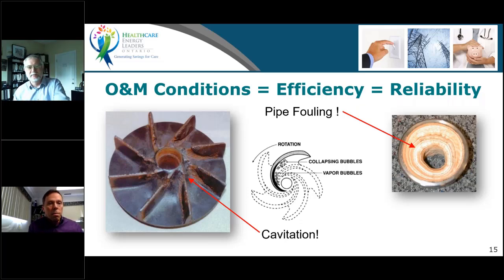The other thing that can happen is the system can change. Now this is a small, I think, 4-inch pipe that had precipitate built up over time. So the 4-inch pipe became a 1-inch pipe. Years and years ago, I had a gentleman come to a workshop that we did, and he had a photograph, and I wish I had taken a picture of it at the time. He had this little 4x6 photograph of an 8-inch pipe on a chiller, on a chilled water system, and he had the same kind of constriction. Now, this was from a dairy, but he was in a hospital. So it's not unusual. It's not impossible to have that occur. Now, that's pretty extreme, but that's going to make that system curve get very, very steep. And if the system curve gets steeper, you're basically throttling the pump, whether you think you are or not.